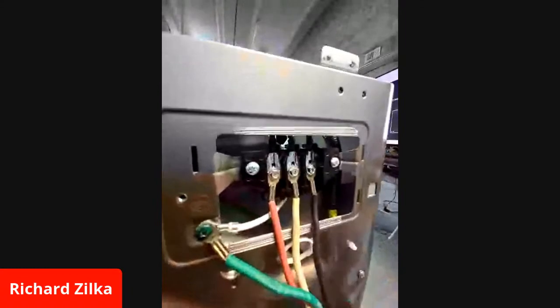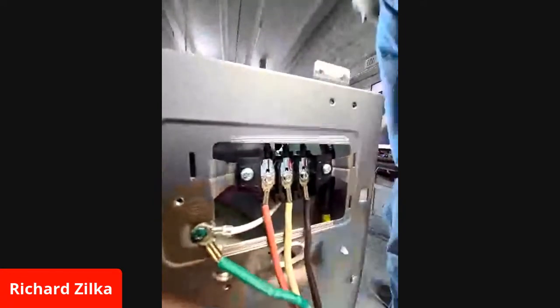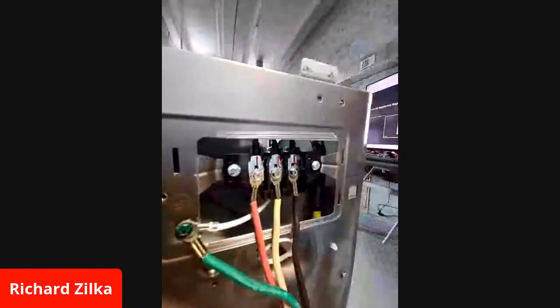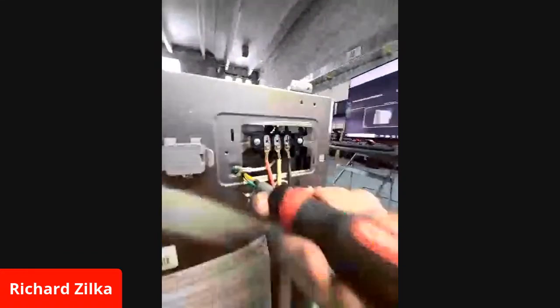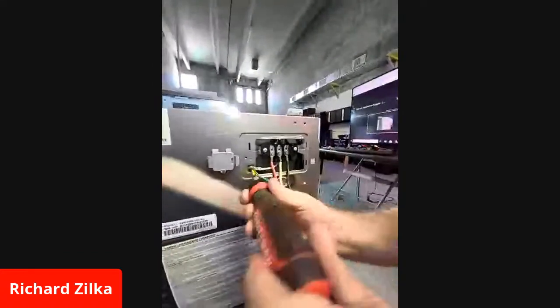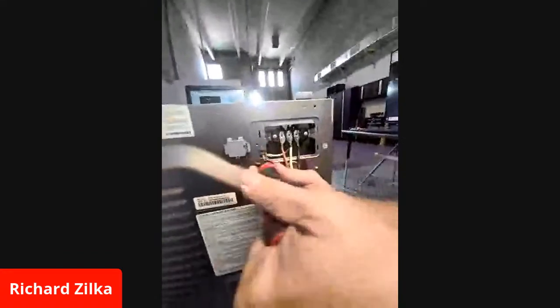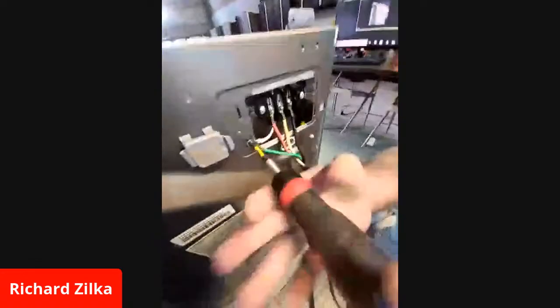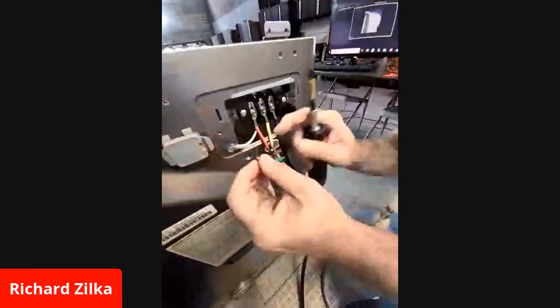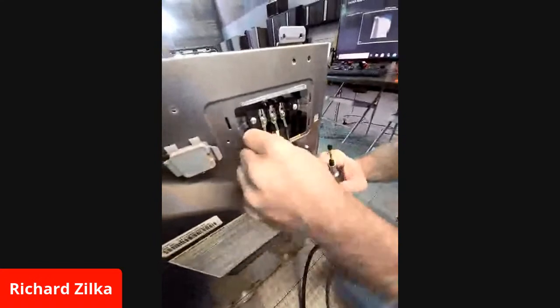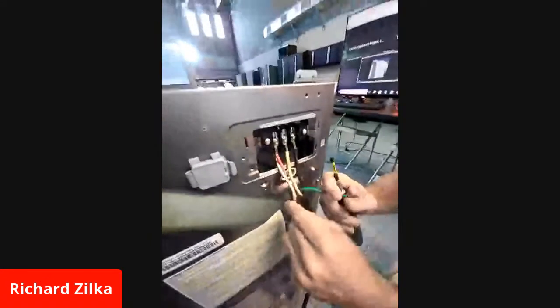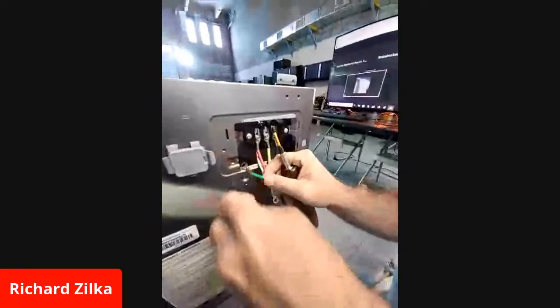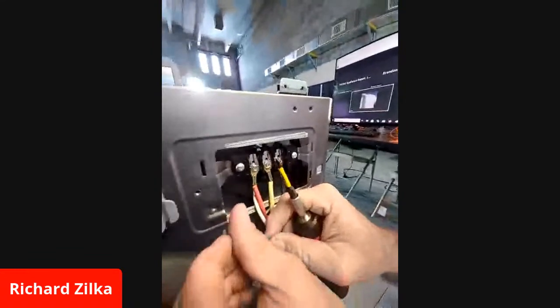So when you're hooking up a 4-wire cord, you have to remove the neutral from here. Back up a little bit, please. You'd actually remove this neutral wire here. This would not be connected. You just tape it off, and you would connect the ground directly to the machine on a 4-wire cord.